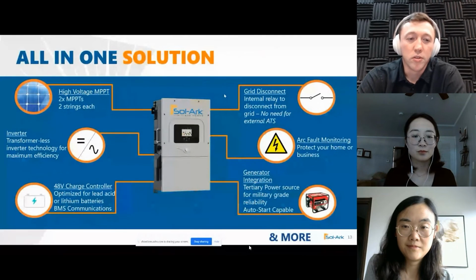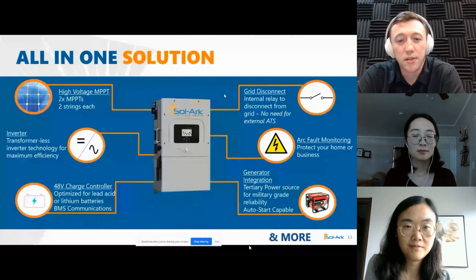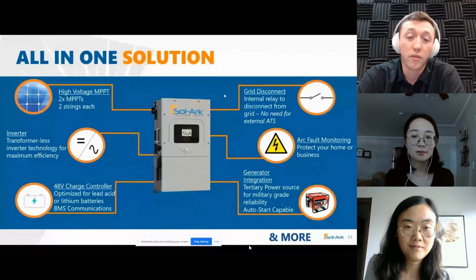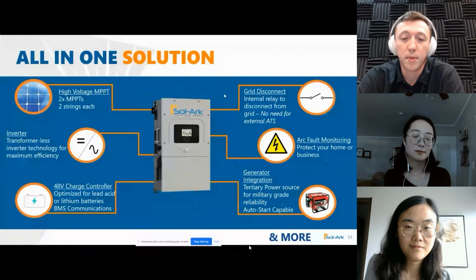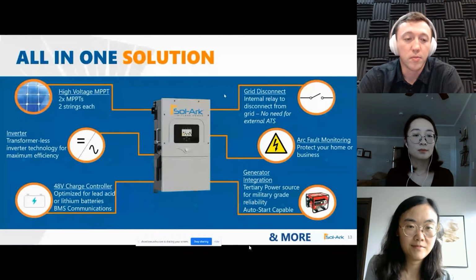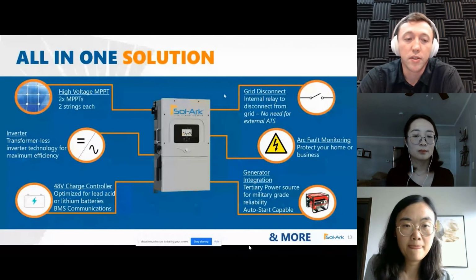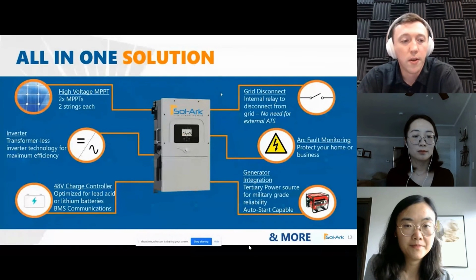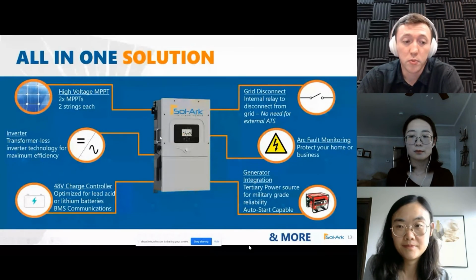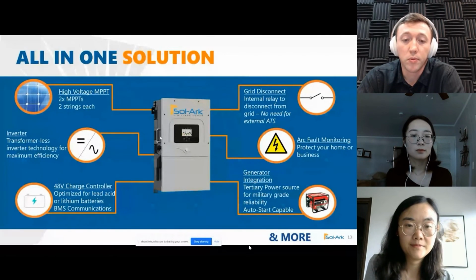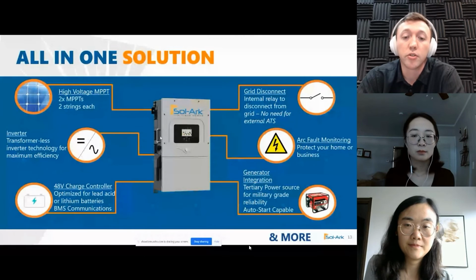Just talking about our all-in-one solution, we have high voltage MPPTs in our Sol-Ark 12K. You have our 5, 8, and 12K. They have 2 MPPTs rated at 6,500 watts each, and then 2 strings of solar can go into each MPPT. So a single Sol-Ark 12K can have up to 4 strings. The 5 and 8K are going to have different values of DC input based off those models. Our inverter is a transformerless technology, and that's made for maximum efficiency compared to the analog transformers, which is going to be a much less efficient inverter.